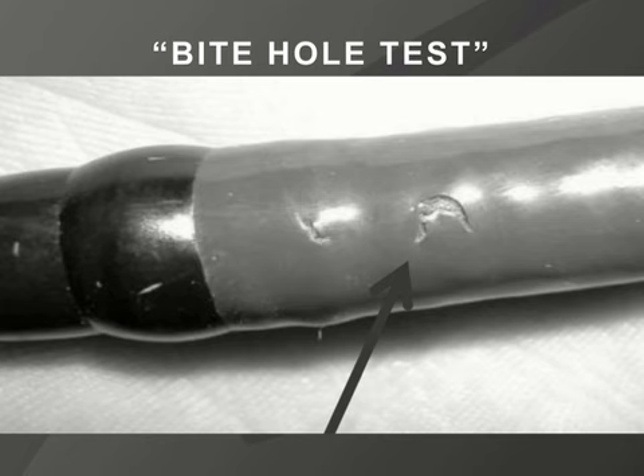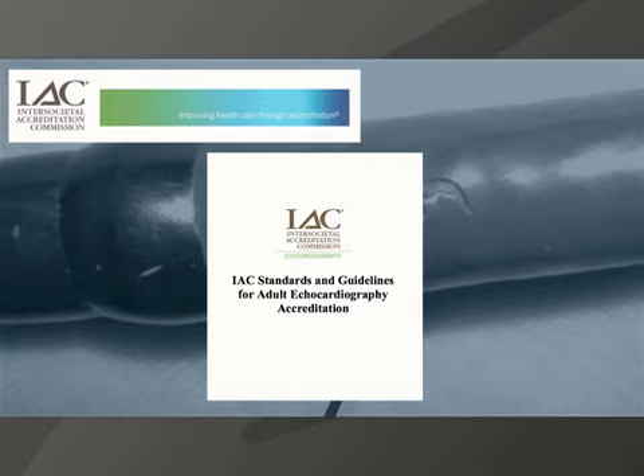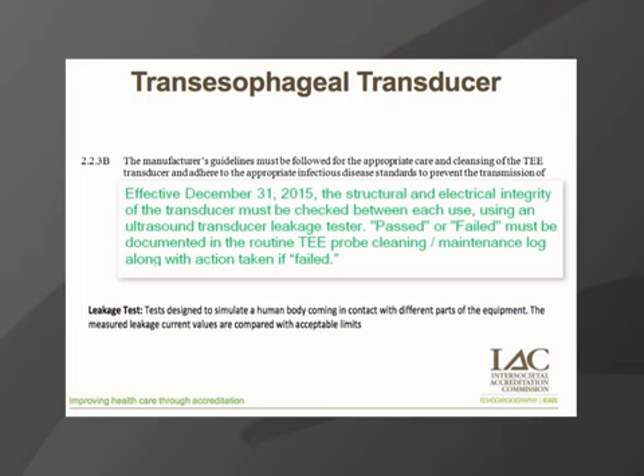Once you have your clean probe, a leak test needs to be done. This is basically a test to check for any leak of electrical current from visible or invisible damage in your probe. Why is this needed? Who mandates this? The Intersocietal Accreditation Commission, IAC, an organization endorsed by many surgical and procedural specialties, including the American Society of Echo. Since 2015, this commission requires that TEE probes are leak tested and that the results are logged and records kept after each use. If your hospital is processing TEE probes, they are doing these tests.